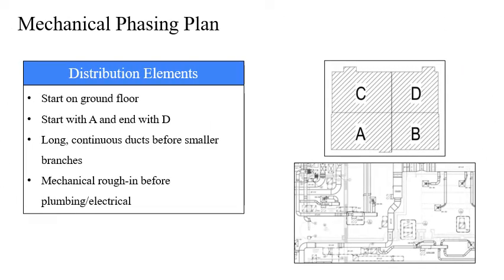The distribution elements will be installed following the equipment installation. This work will start on the ground and tunnel floors in Area A, then move to Area B, then to Area C, and end in Area D. The long continuous ducts in the hallways and large rooms will be installed first. Then the smaller branches will be installed as appropriate. This mechanical rough-in work will need to be completed before plumbing and electrical rough-in, so as not to have any conflicts.